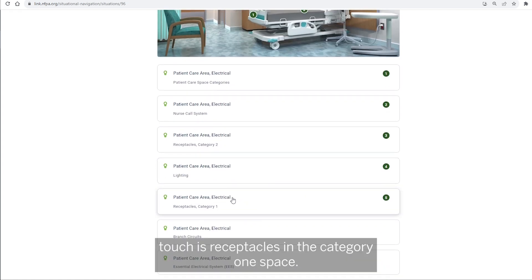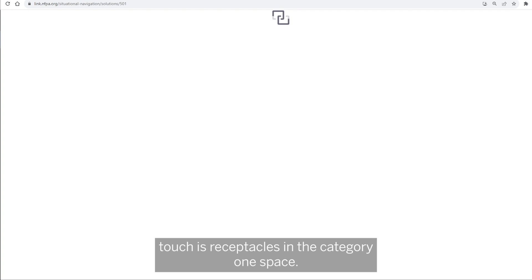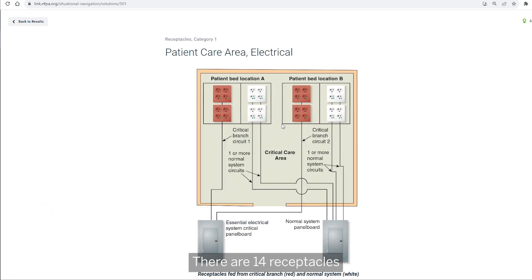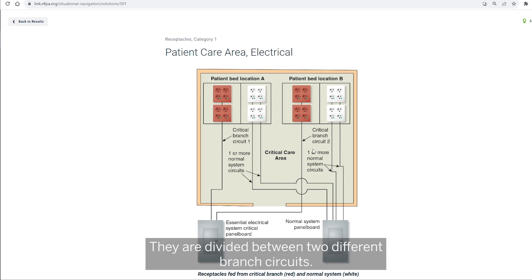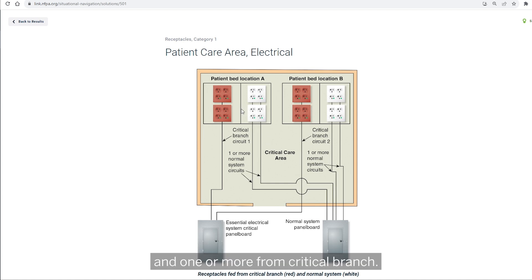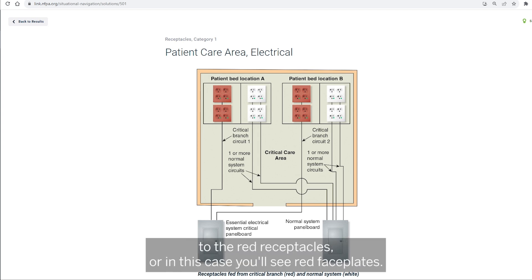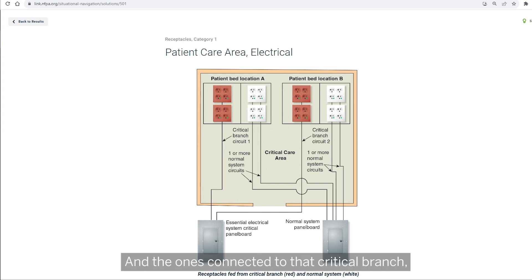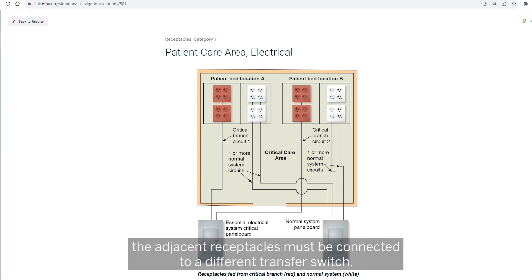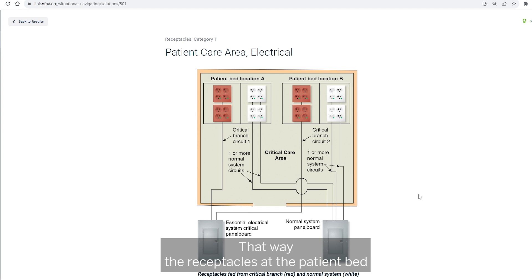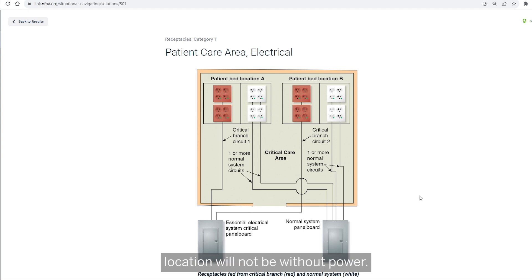The next item is receptacles in the category one space — this requires more. There are 14 receptacles required in a category one space, divided between two different branch circuits. One or more of these circuits can be from normal power and one or more from the critical branch. The critical branch circuits are typically designated by red receptacles or red faceplates. The adjacent receptacles connected to the critical branch must be connected to a different transfer switch, so that the receptacles at the patient bed location will not be without power.